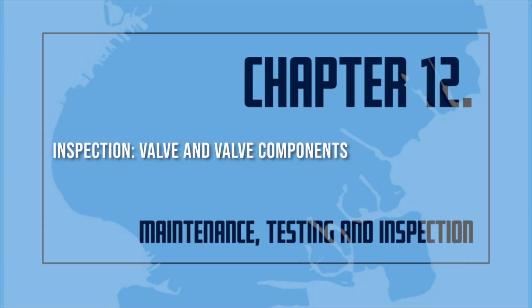Control valves. All indicating valves controlling water supply shall be sealed, locked, or provided with other approved methods as outlined in the National Fire Protection Association No. 25, 2002 edition. A seal is defined as an easily removable device, with no key required, that will indicate the unauthorized operation of a valve. Using this method shall require weekly inspections of each valve by the certificate of fitness holder. All indicating valves controlling water supplies equipped with locks and/or that are supervised shall be inspected monthly. The inspection shall verify that the valve is in the normal open or closed position, properly sealed, locked, or supervised, provided with appropriate wrenches, free from external leaks, and provided with the appropriate identification.